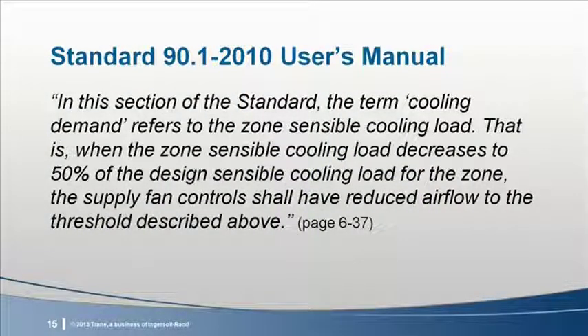The Standard 90.1 User's Manual provides further clarification. It states that the term cooling demand refers to the zone-sensible cooling load. So when the zone-sensible cooling load decreases to 50% of the design load, the supply fan controls must have reduced airflow to at least 1/2 of the design airflow. John will dig into this control sequence in a little bit, but first, let's look at the second part of this section.